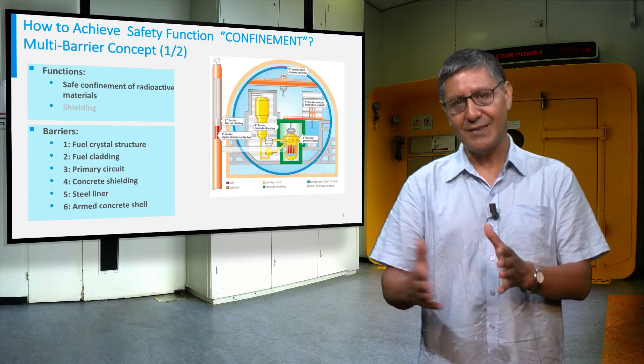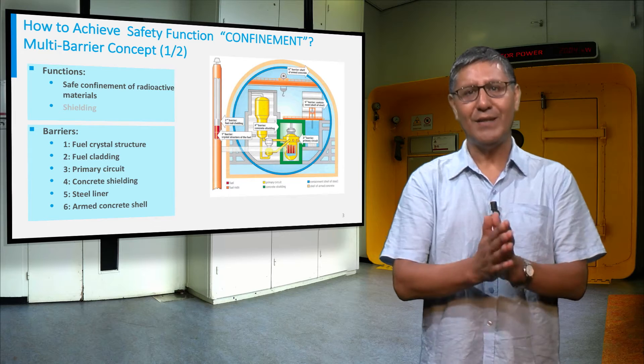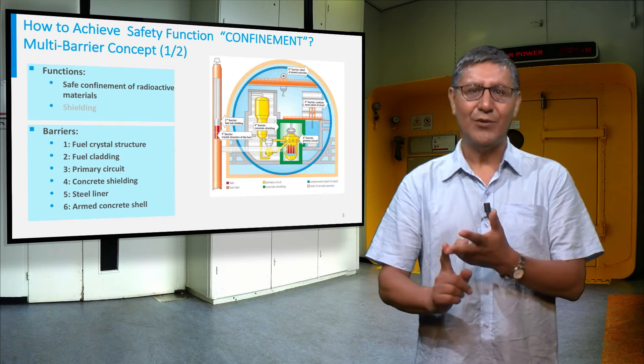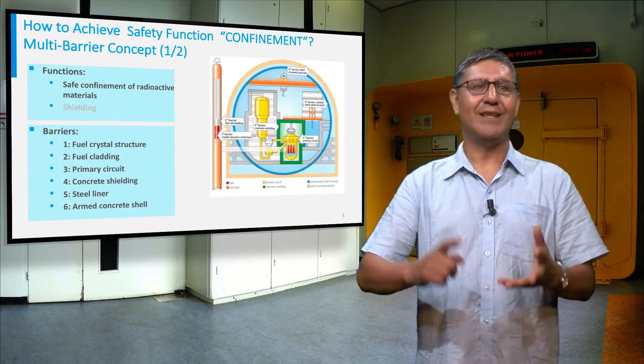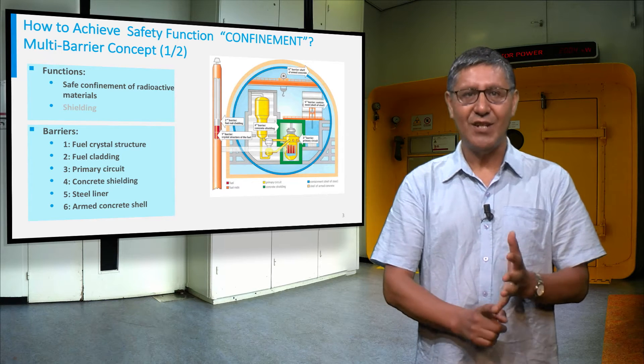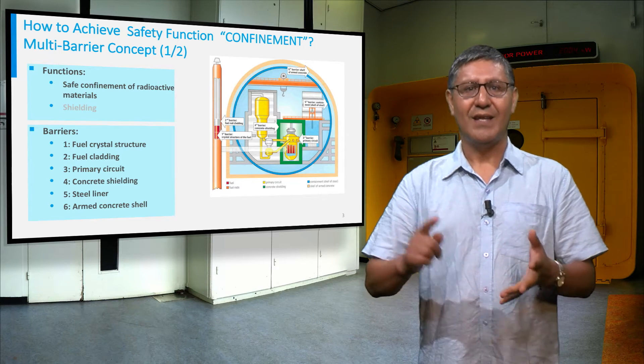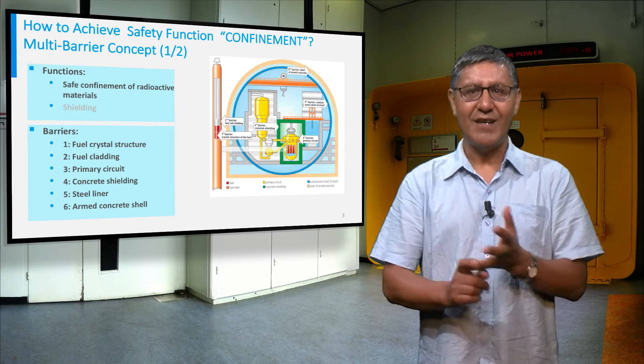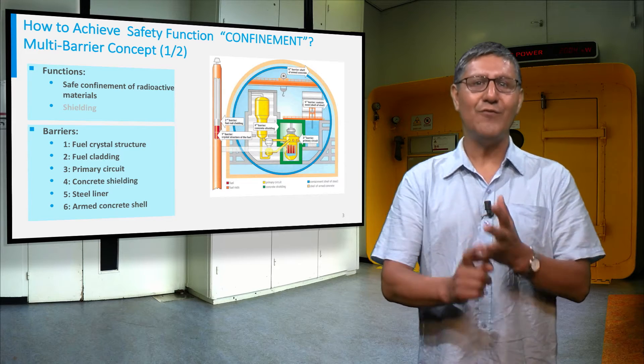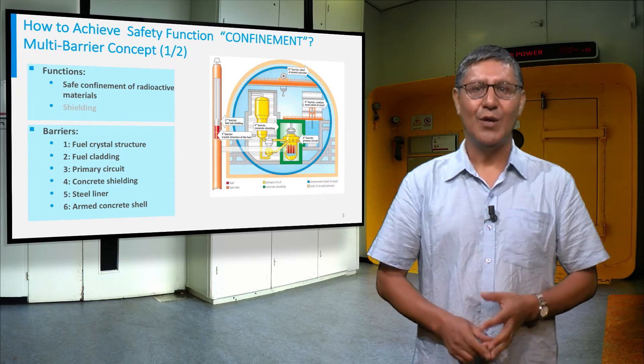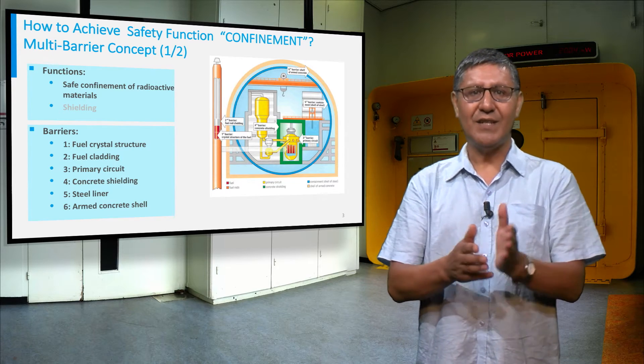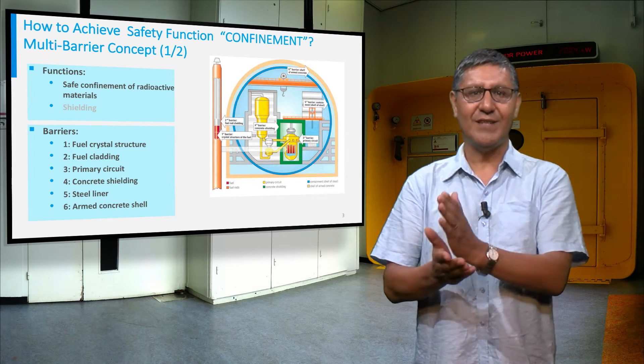These physical barriers are the fuel matrix itself, the cladding, the reactor pressure vessel and the primary circuit, the concrete shielding, and the containment building consisting of an inner steel liner and a reinforced concrete dome. You can see all of these barriers in the figure on the screen.